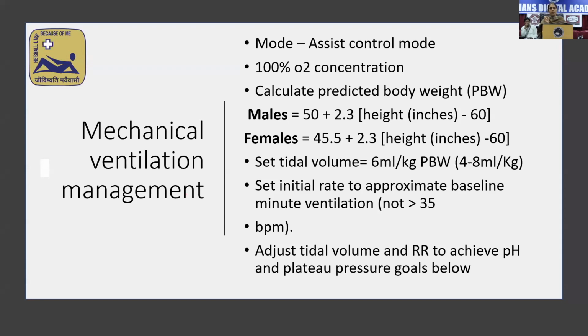Start with 100% oxygen concentration. You will need to calculate the predicted body weight for the patient, which is what is mentioned in the ARDSNet protocol. These are the two formulas that are there. You start with the tidal volume at 6 ml per kg, but the range will be from 4 to 8 ml per kg. You set the initial rate to the baseline. You will have to know the patient's baseline minute ventilation and set the rate accordingly. The rate should not be more than 35.